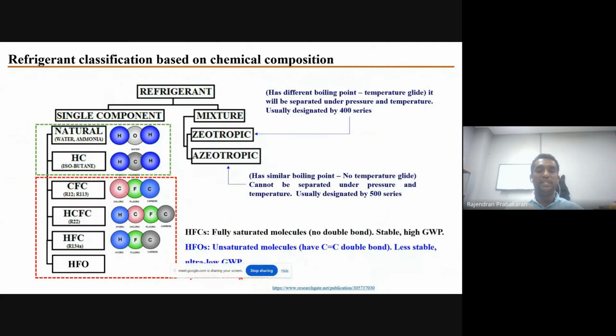So these are the basic classifications of refrigerants based on chemical composition. Under the single component refrigerants, they can be categorized as natural, in which ammonia, water, and others are there, and hydrocarbon based refrigerants, which further include R600A isobutane and R290 propane. And the older ones, that red color indicates synthetic refrigerants, which were earlier used in all kinds of systems, like chlorofluorocarbons R12, hydrochlorofluorocarbon R22, hydrofluorocarbon R134A, and recently, I think a few years back, they introduced another refrigerant based on hydrofluoroolefins. The difference between HFCs and HFOs is the double bond of carbons, which makes an unsaturated molecule, which is less stable in the ambient and also has ultra low GWP as compared to HFC refrigerants.